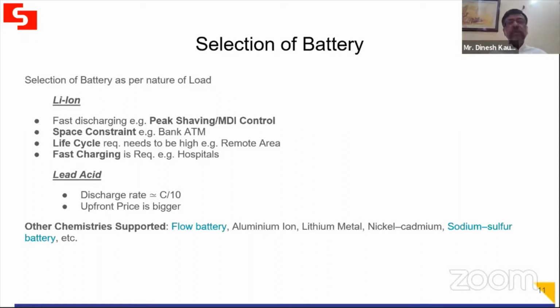So we were just talking about peak shaving and MDI control. Now both of these require a quick discharge of the battery. How do we do that? Not with lead acid, because the lead acid discharge rate is C/10—you can only discharge it over its full capacity in 10 hours, which is slow. But a lithium ion battery, you can charge or discharge very, very fast, making it the ideal chemistry for peak shaving and MDI control. That is another economic sense.